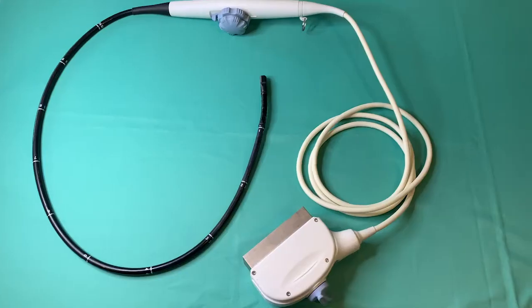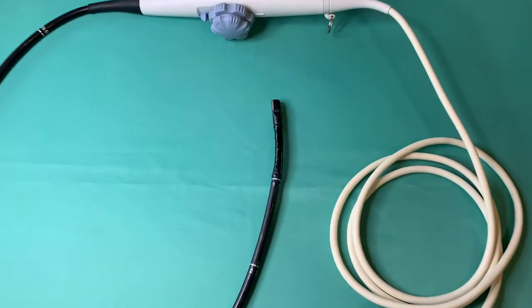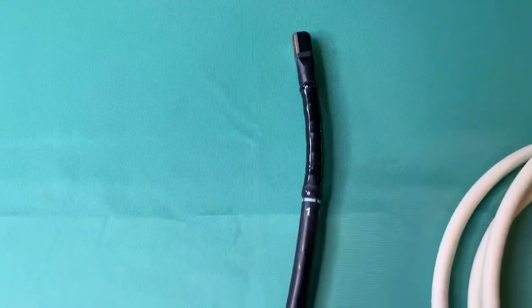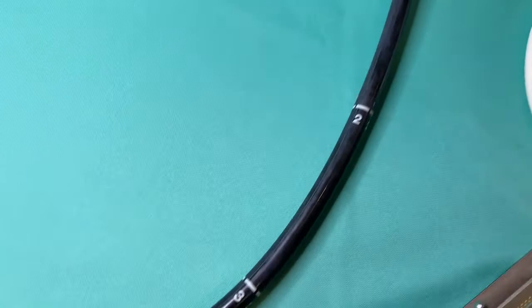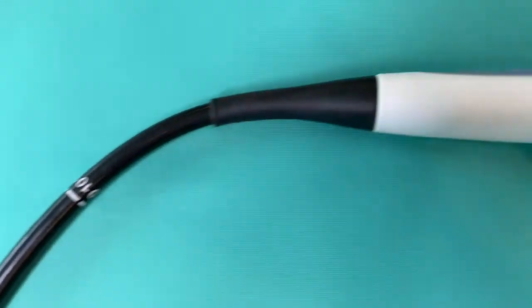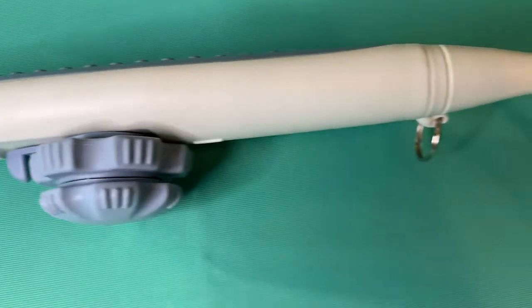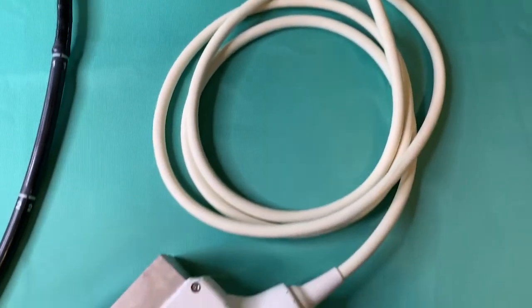Today we're going to do a demonstration on how to perform a preventive maintenance inspection on a TEE probe. A thorough visual inspection is the first step of a PMI. It's best to begin at the distal tip, work your way down the insertion tube, across the control body, ending at the system connector. Starting at one end and ending at the other will prevent potentially skipping important areas of the probe.